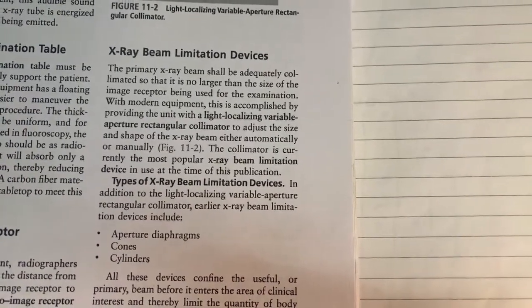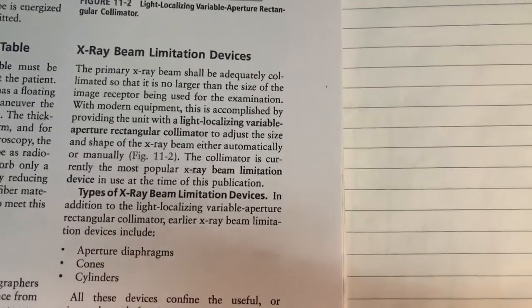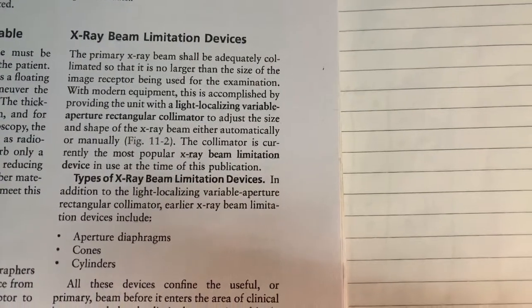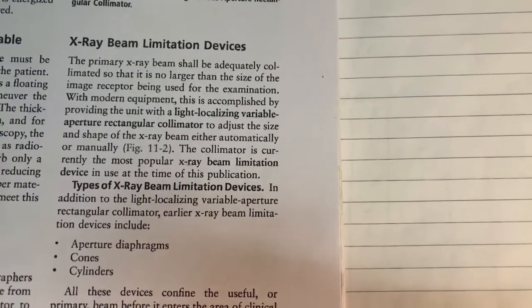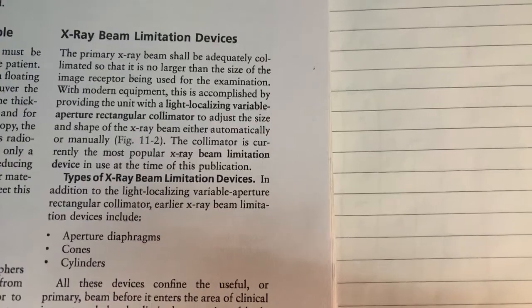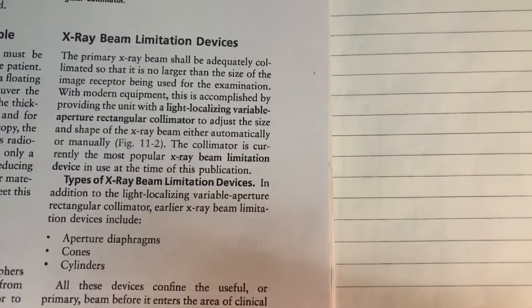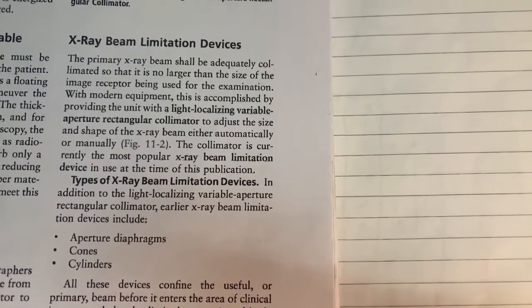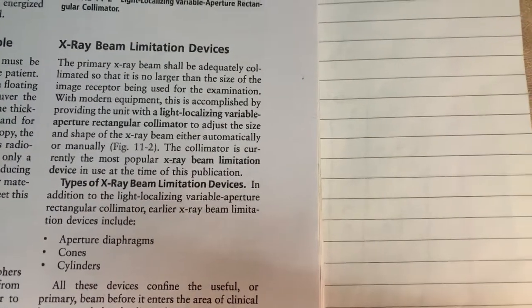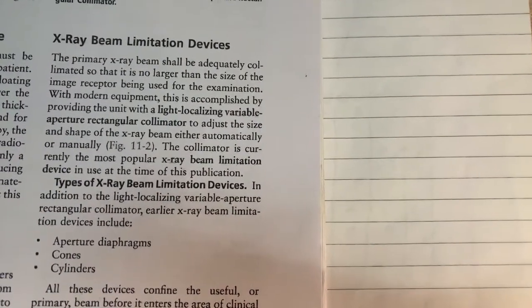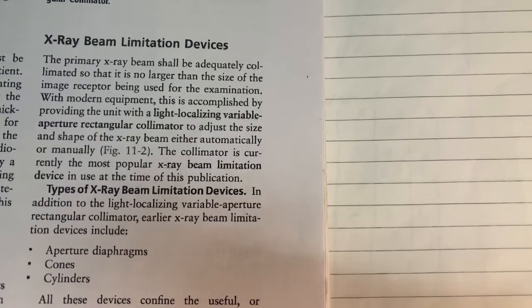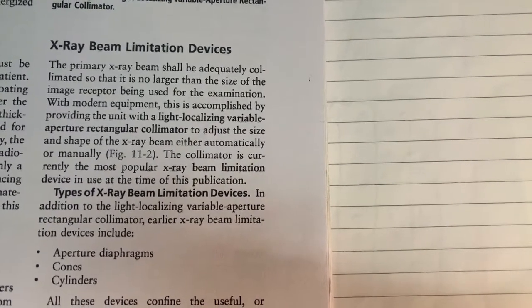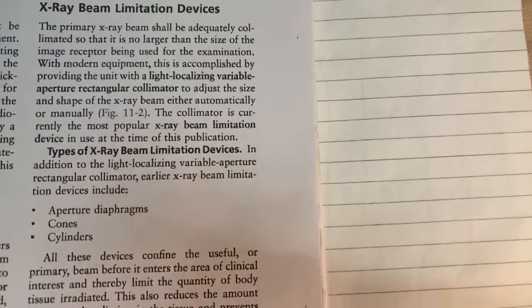With modern equipment, this is accomplished by providing the unit with a light localizing variable aperture rectangular collimator to adjust the size and shape of the X-ray beam, either automatically or manually. The collimator is currently the most popular X-ray beam limitation device in use.